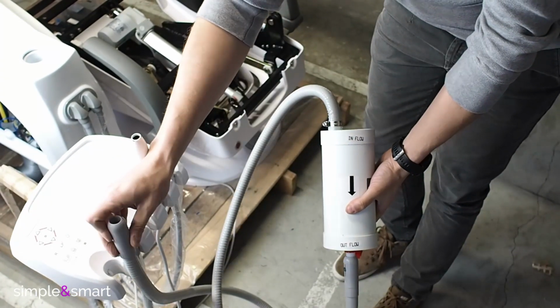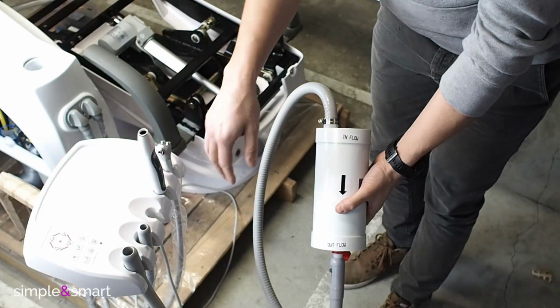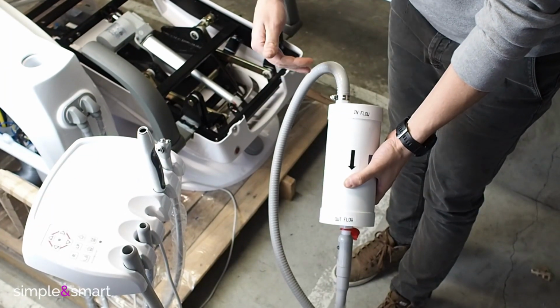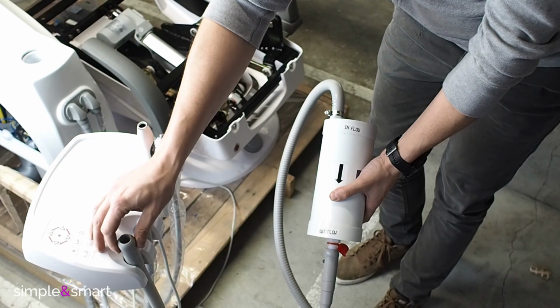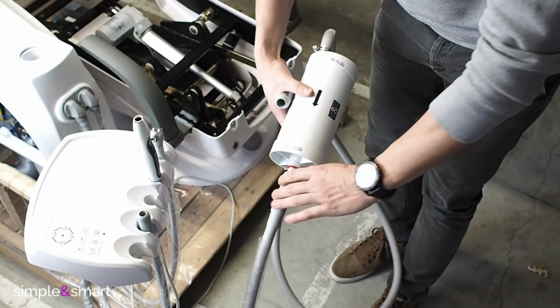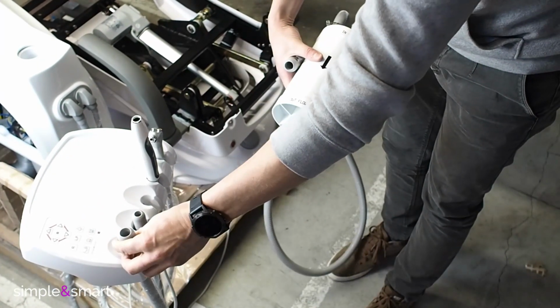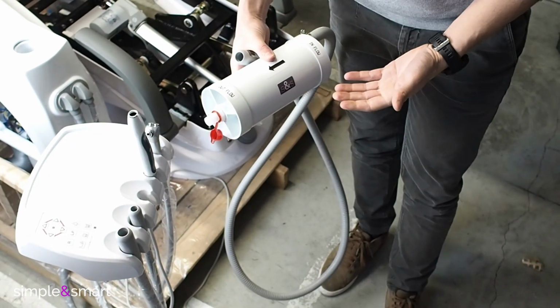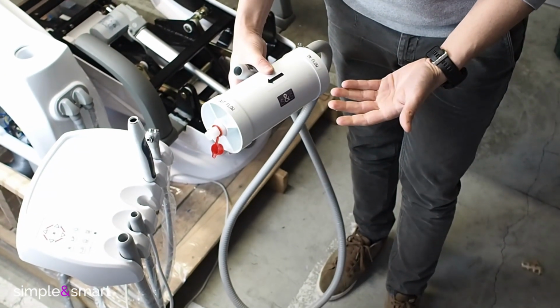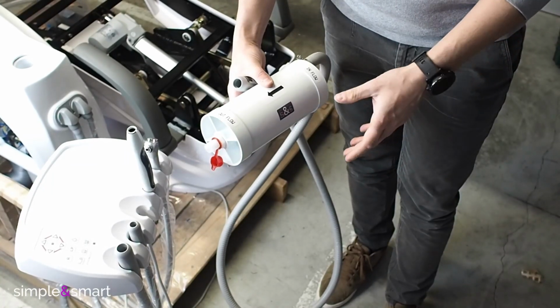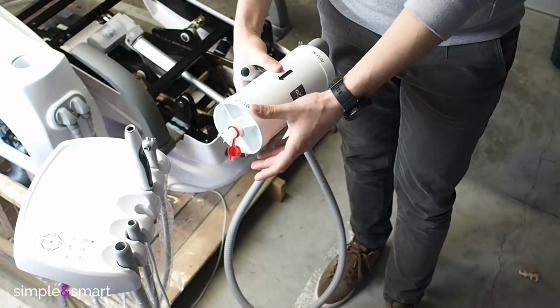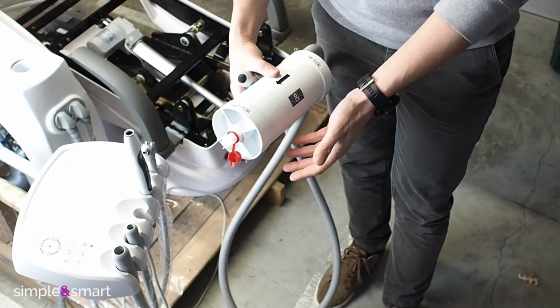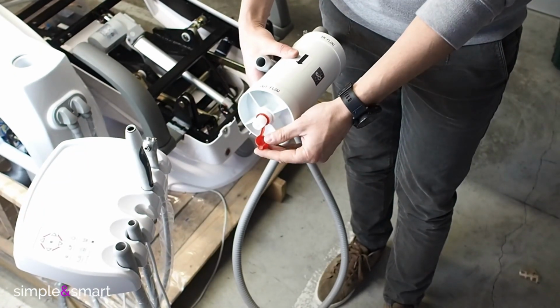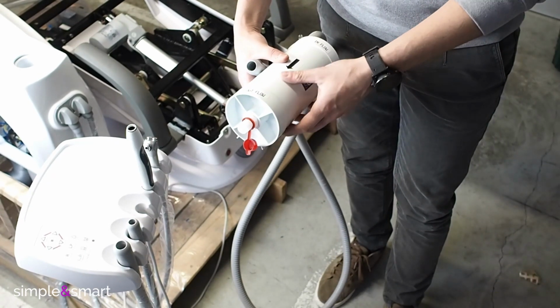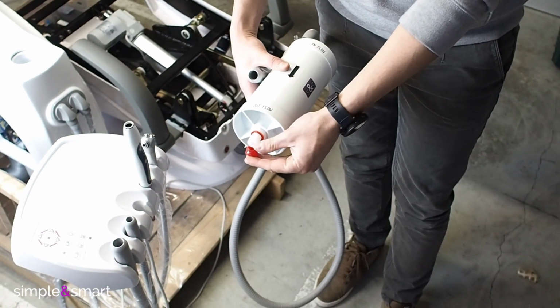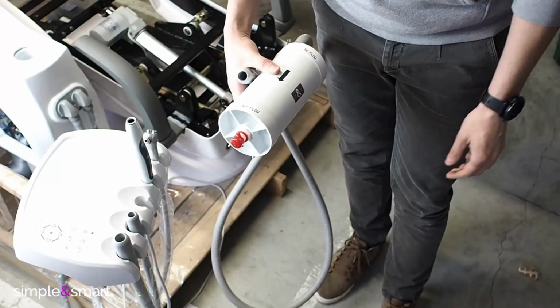So you can use and attach the cannula that we provide already in the assistant tray. When you have finished, you take out the cannula and you put back your cannula inside the instrument tray. So this situation is easier because you can apply it in all the dental chairs that you have, and you don't need any installation, and you are sure to get all the amalgam that you need to put inside the filter without any waste of filter life. When you finish, you close the tap and the game is done.